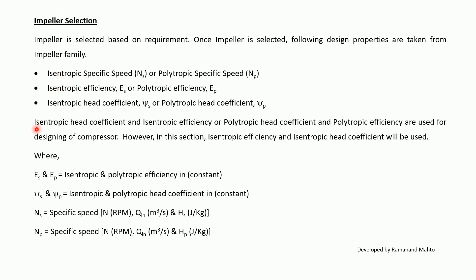Either a set of isentropic efficiency and isentropic head coefficient or polytropic efficiency and polytropic head coefficient can be used. In these sections, isentropic efficiency and isentropic head coefficient will be used. ES and EP are isentropic and polytropic efficiency; psi_S and psi_P are isentropic and polytropic head coefficients; Ns and Np are specific speeds. For Ns, N is in RPM, Q is in m³/s, and HS is isentropic head in J/kg. For Np, HP is polytropic head in J/kg.